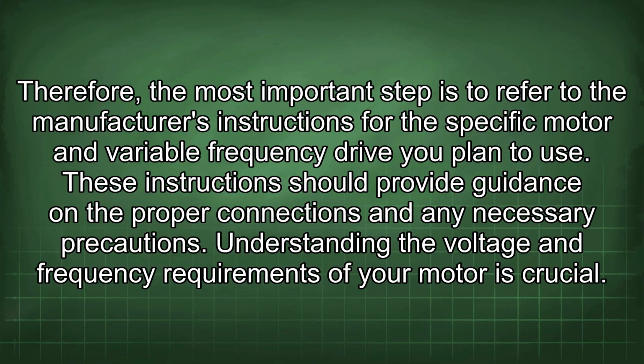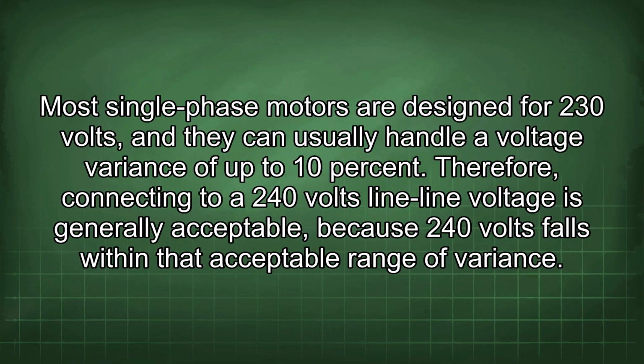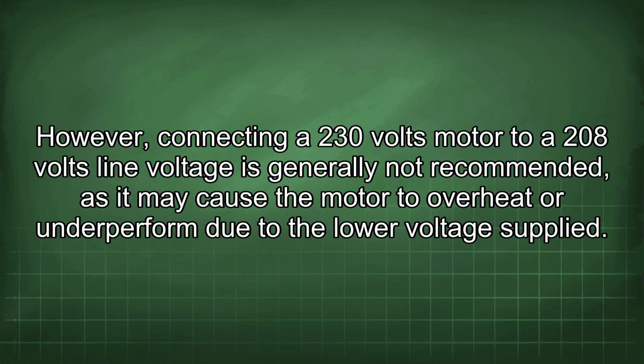Understanding the voltage and frequency requirements of your motor is crucial. Most single-phase motors are designed for 230 volts, and they can usually handle a voltage variance of up to 10%. Therefore, connecting to a 240 volt line voltage is generally acceptable because 240 volts falls within that acceptable range of variance. However, connecting a 230 volt motor to a 208 volt line voltage is generally not recommended, as it may cause the motor to overheat or underperform due to the lower voltage supplied.